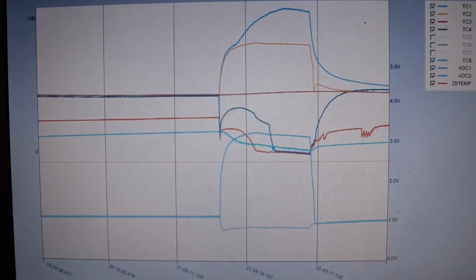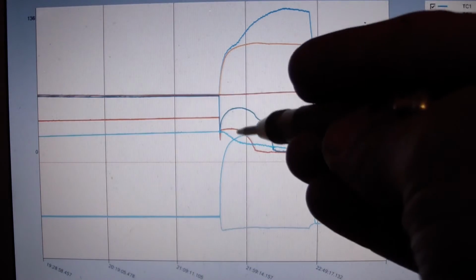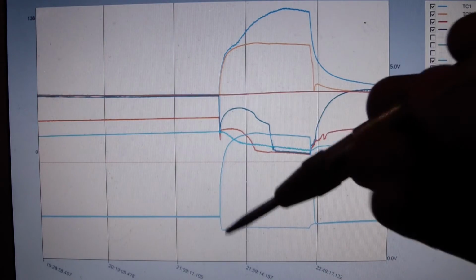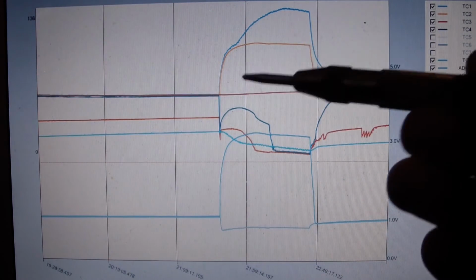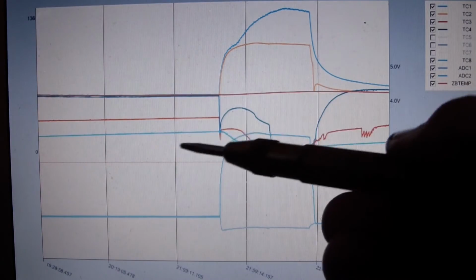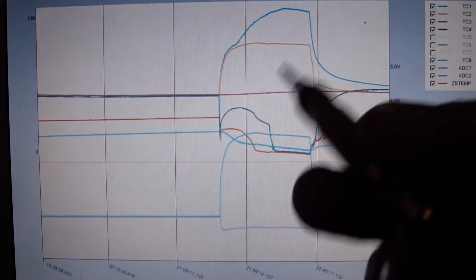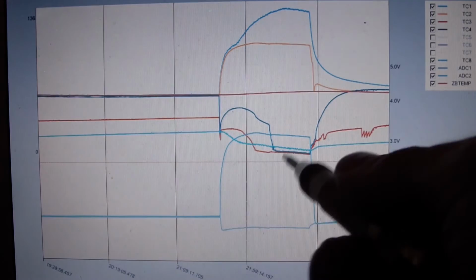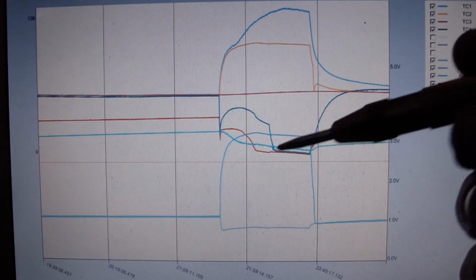liquid flows a lot better through a cap tube. So we're not feeding the evaporator sufficiently for the heat load that's required. So we have that reduced mass flow rate at the cap tube as well. So this goes on for about half an hour until things get in the groove, we'll say.